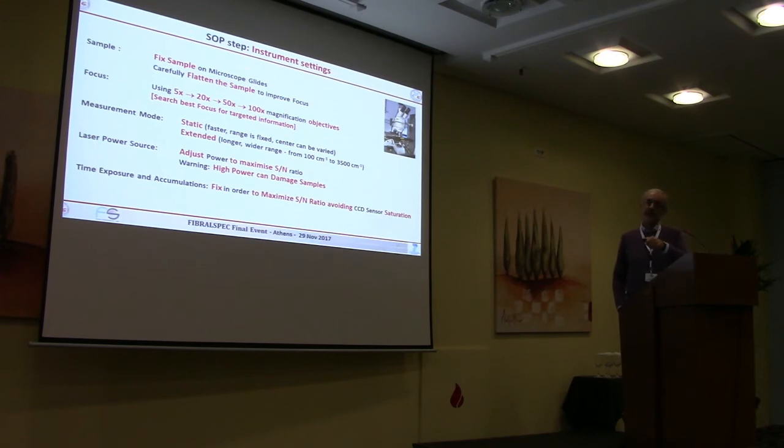Then the first step in the SOP, once you have defined your wavelength, is to set the instrument. There are a number of things you have to be careful about, which I have summarized here. Each of them needs a discussion and comparison with partners. So you have to fix the sample properly, and you should try to flatten it because you have to focus. If it is not well flattened, you are not getting an appropriate quality signal. And then the best procedure is to go for successive focuses and then stop at the one you want.